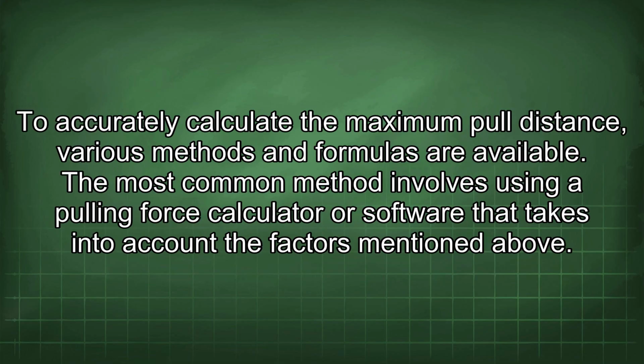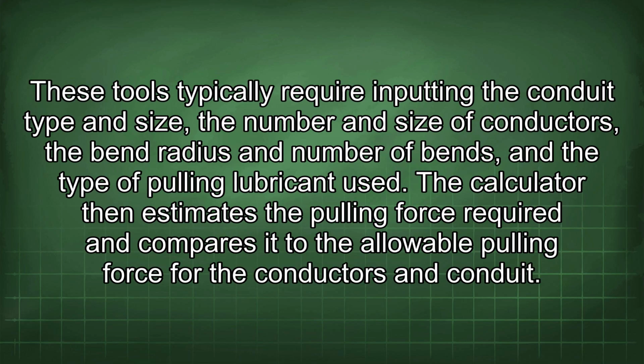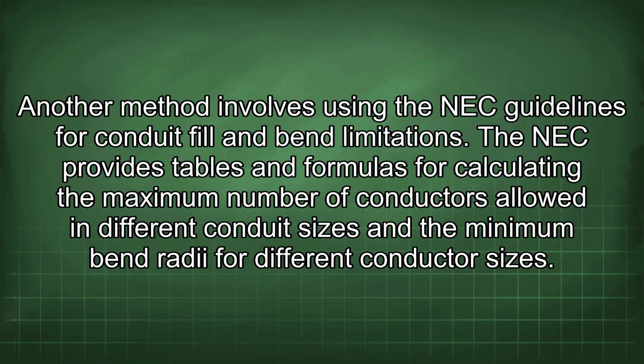To accurately calculate the maximum pull distance, various methods and formulas are available. The most common method involves using a pulling force calculator or software that takes into account the factors mentioned above. These tools typically require inputting the conduit type and size, the number and size of conductors, the bend radius and number of bends, and the type of pulling lubricant used. The calculator then estimates the pulling force required and compares it to the allowable pulling force for the conductors and conduit. Another method involves using the NEC guidelines for conduit fill and bend limitations.